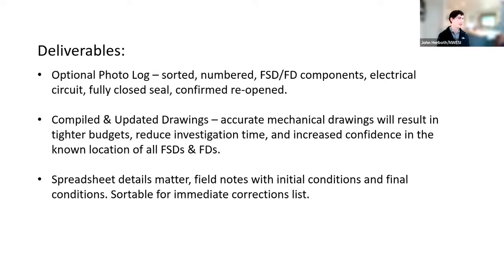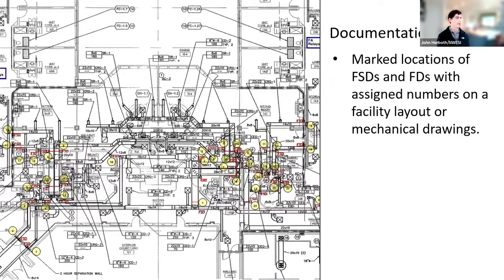Then compiling drawings and spreadsheets, the details matter when it comes to this type of stuff. We also note the access grade, what size of ladder they need, and whether you need to turn off a fan to test it. Code-wise, you're supposed to test all this type of stuff at pressure. But as commissioning and TAB providers, I don't know if you've walked into a building and ever trusted safety relief or pressure safety devices.